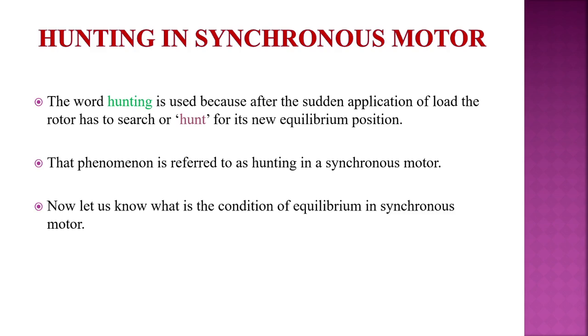So in some cases when the mass of the rotating parts has an oscillating period that is the same as or a multiple of the hunting period, mechanical resonance is set up and the amplitude of the swing of the rotor poles relative to the poles of the rotating field will become so great that either the rotor circuit gets opened by the circuit protective devices or the motor falls out of synchronism and stalls. So hunting is nothing but an objectionable characteristic of all synchronous motors.